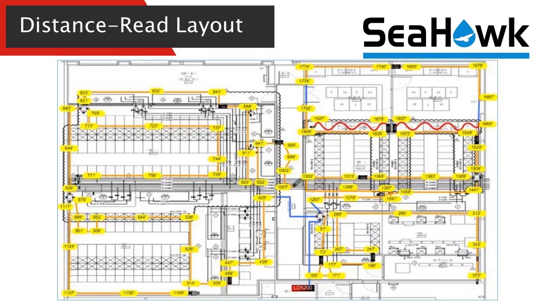Here's an example of one of the integrated maps for the distance read leak layouts. If you notice on the bottom in the middle, there is the LD5200 with the blue wire coming out of it, leading up to an X connector, which then splits out in 3 different directions. So that's a good example of how an X connector can be used. Each leg is also going to have 50 feet of simulated resistance. So again, we're isolating which areas and directions everything's going, so that you ensure that when a leak does occur, you're sending the appropriate maintenance personnel to the proper area without any question of knowing where it originated.